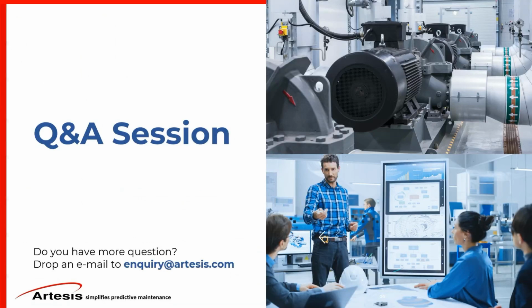I mentioned that we are doing machine learning within 7 to 10 days. During that 7 to 10 day learning period, the system will learn each operation point of the rotating asset. This doesn't have to be a pump. It can be anything. And it will learn and create clusters, basically a digital twin for every operation point of the system.